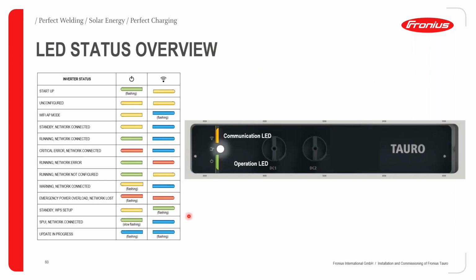Good. In the case of LED status, we have color codes indicated by the respective LEDs, that is the communication and operation LED. This color code gives us indications of the inverter status. For example, in this case, we have the communication LED on yellow and the operation LED on green. Looking at the color code, for green and yellow, that is operation and communication respectively, it simply means that the inverter is running but the network is not yet configured.